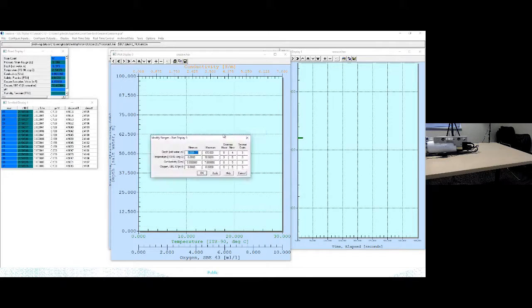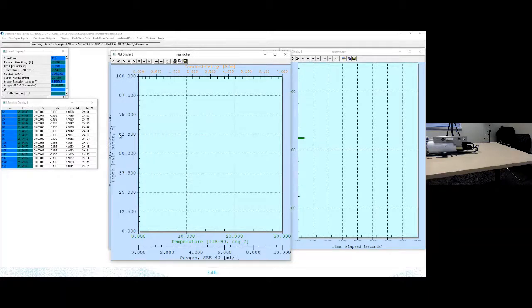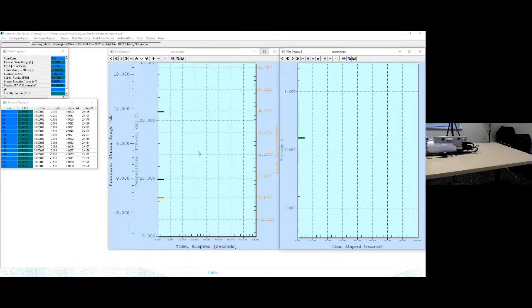You can do things like modify the ranges. So in this case, this has depth on the y-axis, but since we're not doing a profile, I'm going to look at pressure on the y-axis and time on the x-axis. And this is showing me all of the data I have coming in from this CTD into Seasave. Not very interesting. This is basically telling me that in air, the room temperature is around 21 degrees C and there's zero conductivity. So that's pretty much as we would expect.